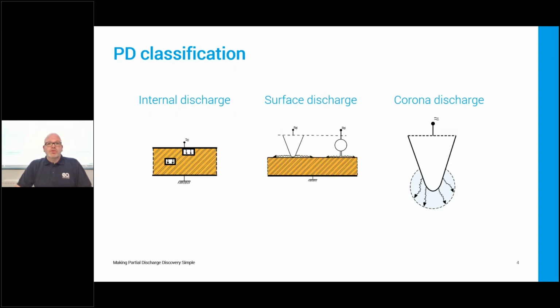This slide reinforces how we classify PD with the help of some nice diagrams. Internal discharge, you can see where that can occur within voids inside insulation, so a HV cable, for example. Surface discharge, again, is where the discharge tracks across the surface of the insulation. And the last picture shows corona discharge, which essentially is caused by the ionization of air around a conductor. Mostly this is not an issue, perfectly natural on some outdoor assets, overhead lines, that sort of thing. So mainly it'll be internal and surface discharge we're looking for when, for example, we're undertaking a PD survey.